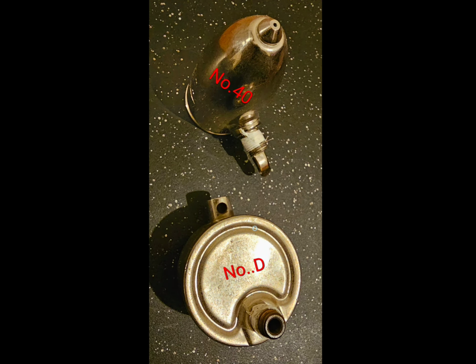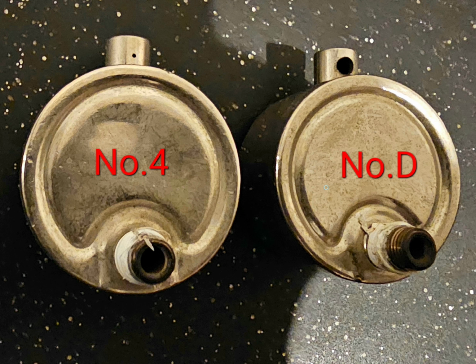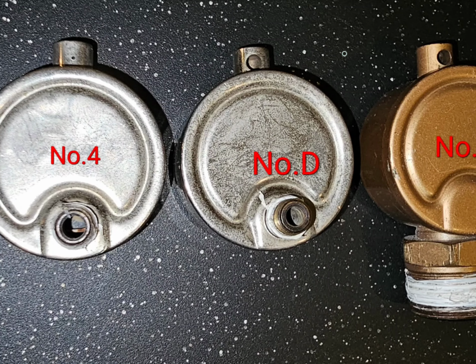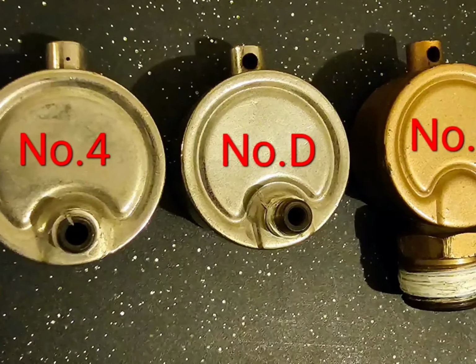This is the way every single vent that you see demonstrated or showcased in any of these images that I took, which is what this is in my archives, in my arsenal or roster, if you want to say. Every last one of these vents has that same thermostatic element inside of it, which also serves the purpose of being a float. This is why with the Gorton's number D, you can blow into it, and if you get a significant amount of wind volume going through it, you will lock the float in the closed position. It's the same with every last one of them, from the number 1 to the number D to the number 4. They all have that same thermostatic element, which also is a float.